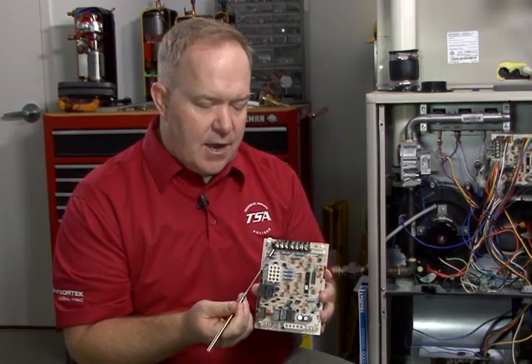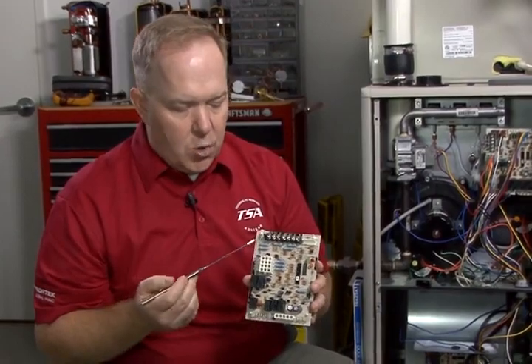You set up the basics on the thermostat so that the system can be tested and operated, and then that's it. They never do actually invest the time to read through the installation manual or the setup procedure on their thermostat, and that's where it sits for the remainder of its life, and it's not performing to its optimal levels when that thermostat is not set up properly. Another option that you have now on our 2-stage gas furnaces can really easily take away a lot of that guesswork for the homeowner.